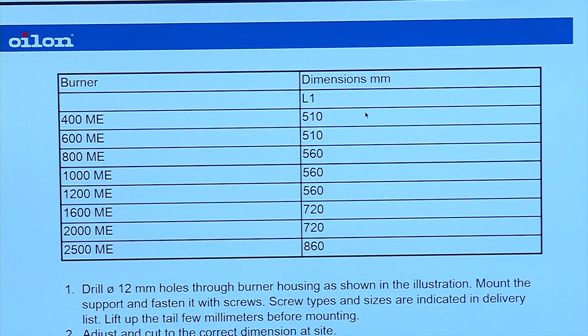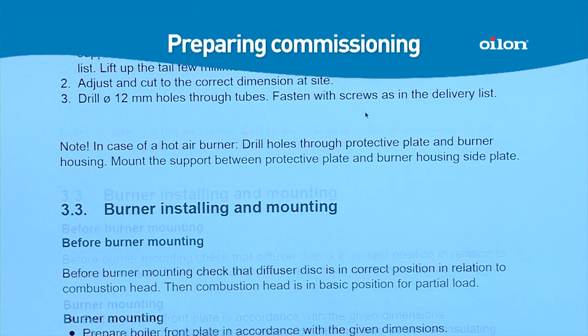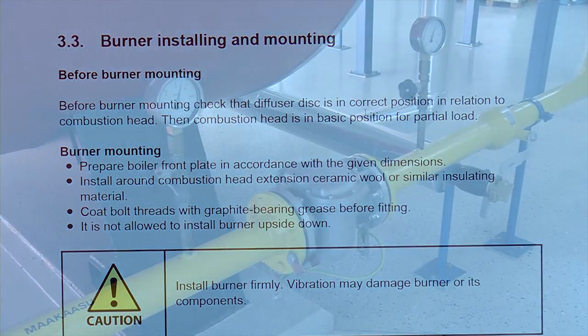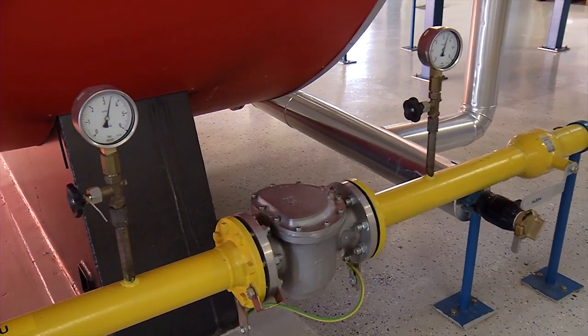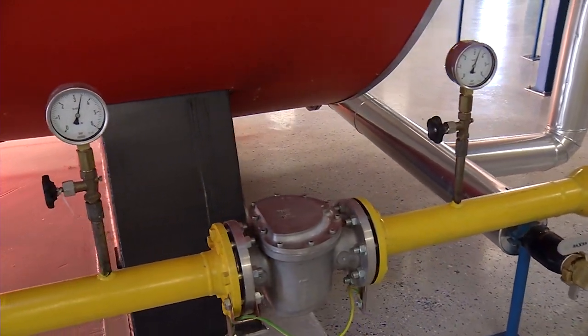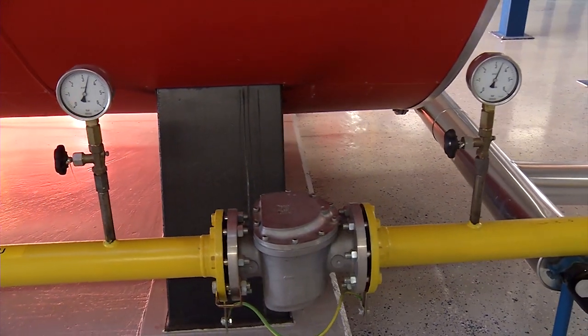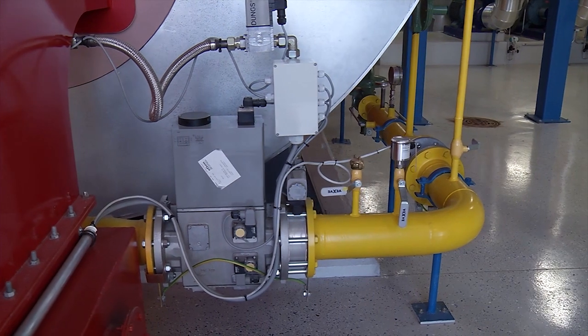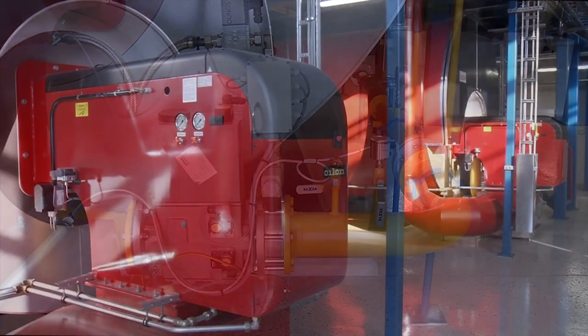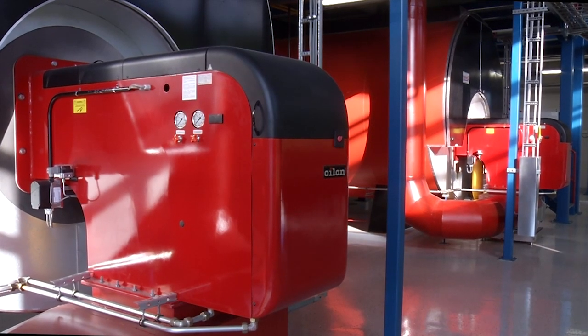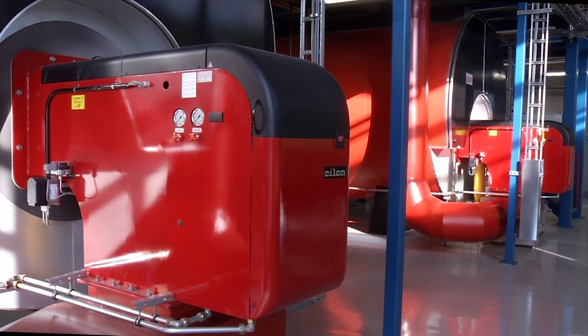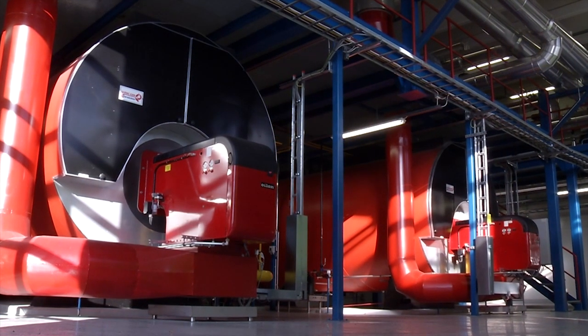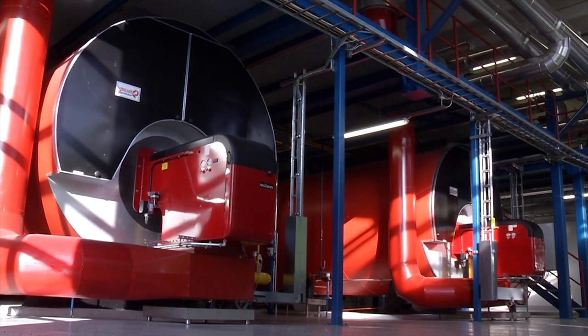In the burner manual you can find detailed instructions for installing and mounting the burner. Make absolutely sure that the fuel piping and installation are laid according to the regulations of local authorities, and that the burner is connected according to the electrical diagrams delivered with the burner. Pay special attention to the requirements for electrical equipment and their connections. Ensure that plant grounding is done correctly before commissioning the burner.